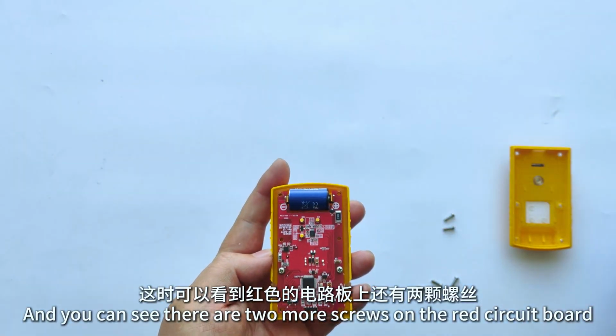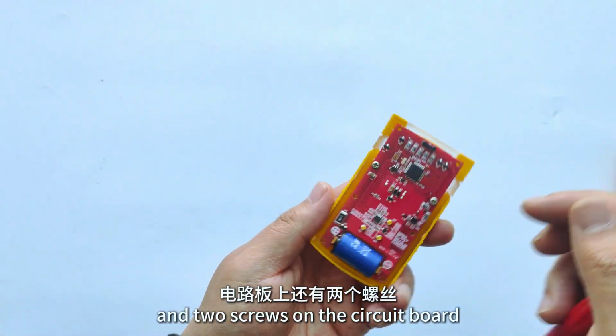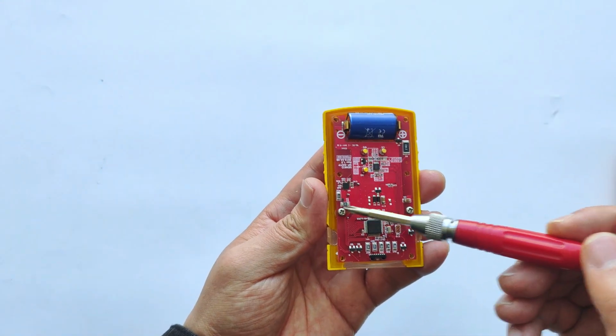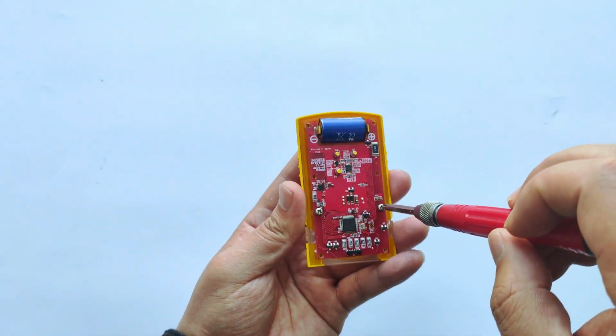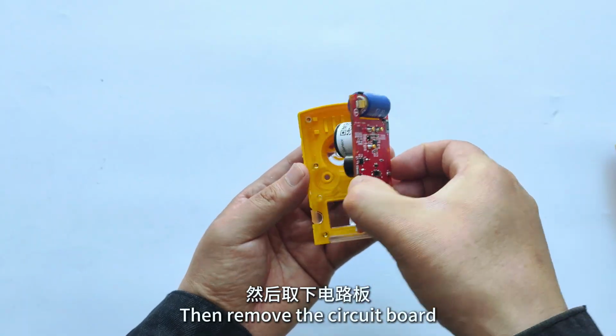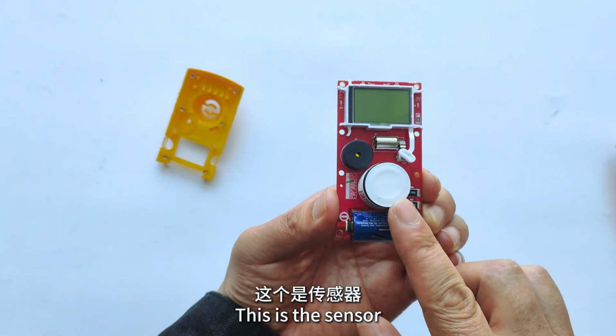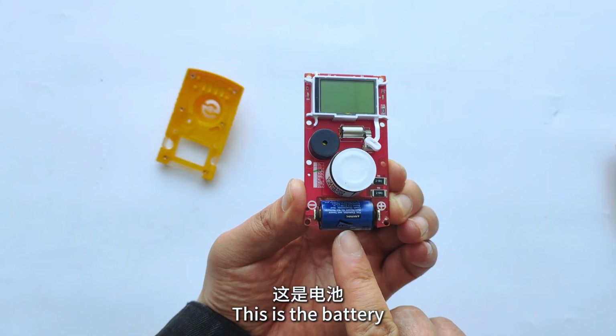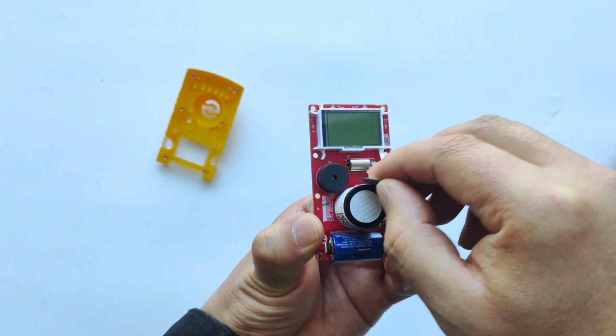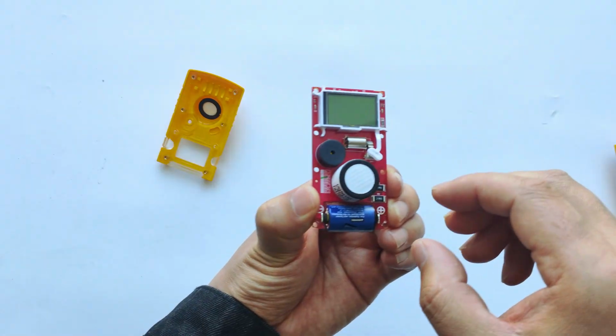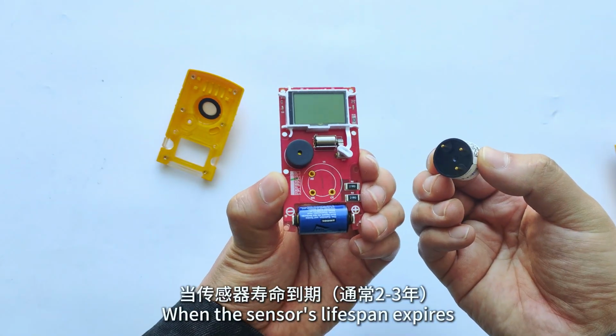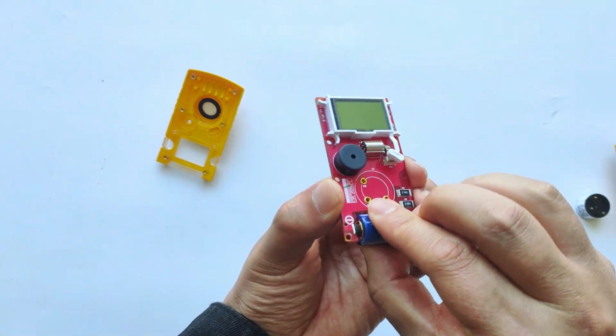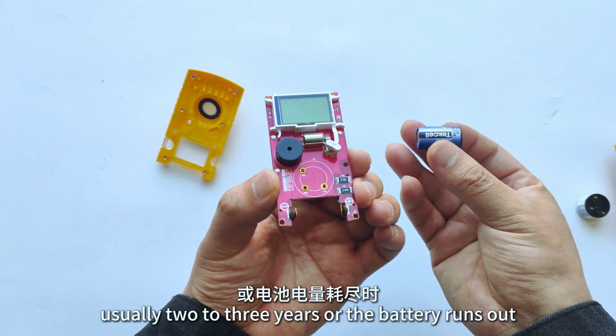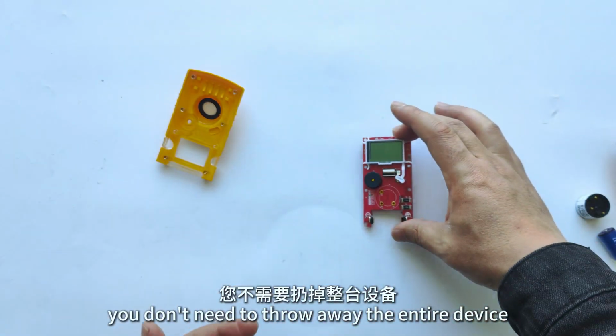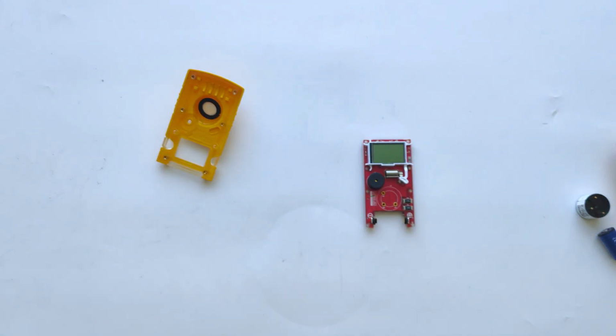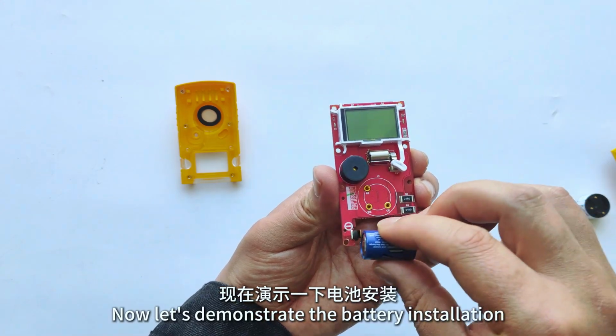And you can see there are 2 more screws on the red circuit board. Then remove the circuit board. This is the sensor. This is the battery. When the sensor's lifespan expires, usually 2 to 3 years, or the battery runs out, you don't need to throw away the entire device. Just buy a replacement. Now let's demonstrate the battery installation.